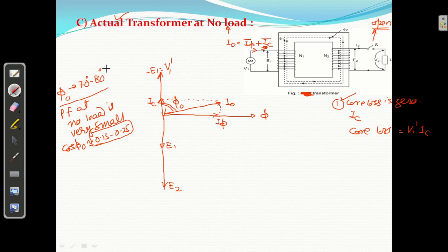Is it clear why the angle is between 70 to 80 degrees? You can see this angle, because the magnitude of this is more than IC. So the greater Iφ is and the smaller IC is, the more I0 will be. Okay, so this is I0 and this is phi 0. Phi 0 is 70 to 80 degrees, which means the power factor at no load is 0.15 to 0.25, right?